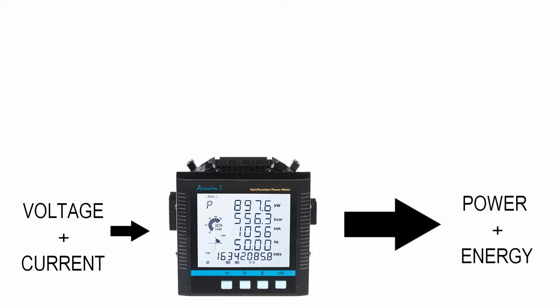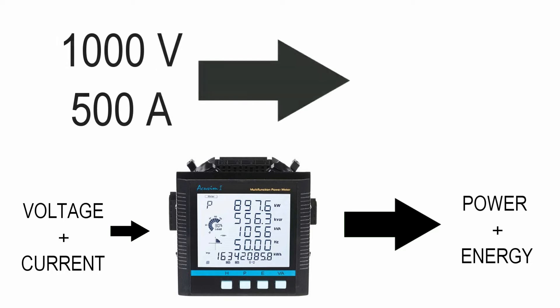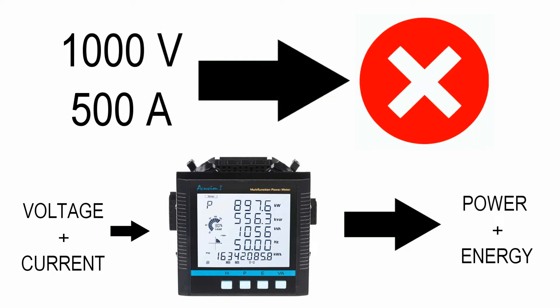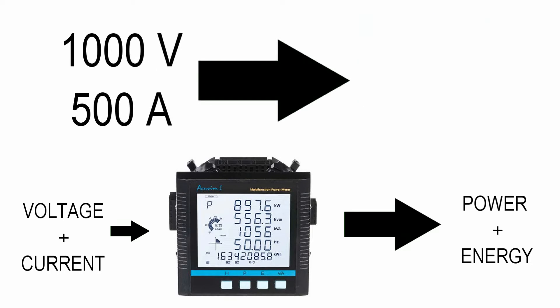However, for example, if you directly connect a thousand volts with 500 amps to the meter, it will burn out the meter. As a result, the voltage and current must be stepped down before you feed it into the meter. The devices for that are called potential transformers or PTs and current transformers or CTs.